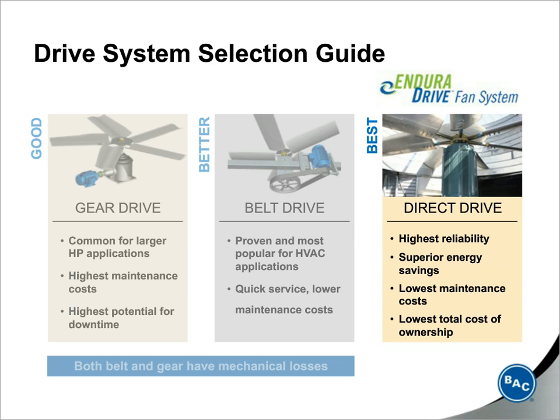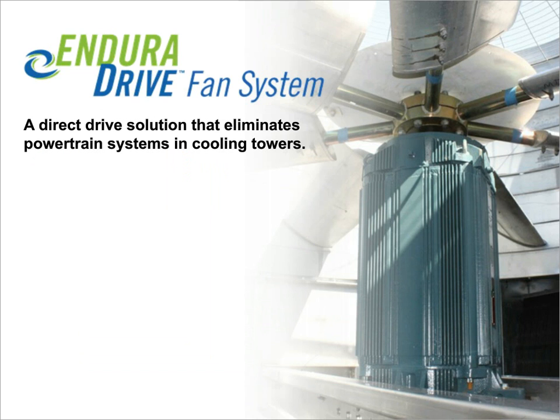Now, however, there have been recent developments in technology that have made direct drive much more practical and much more cost-effective for factory-assembled cooling towers. Direct drive technology can now actually replace the traditional drives, both belt and gear, and it offers benefits that weren't available before. There's far greater reliability than traditional drives. Since there aren't any couplings or shafts, direct drive completely eliminates misalignment issues that occur with gears. And you definitely don't expect any coupling failures, because there aren't any couplings to fail. Instead, with the direct drive system, the fan is mounted directly to the motor shaft.